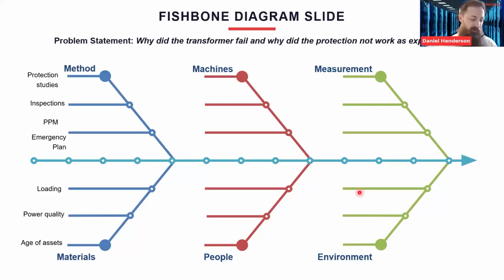The classic loading of the assets, people adding a bit here, a bit there, and whoever's ultimately in charge of the network or responsible for it is never informed until eventually you get to the overload point. But definitely some good considerations. Load subtraction should also be taken into account. Again, something to take into consideration is the loading element and especially power quality, because obviously a lot of the networks, especially back then, were designed for direct online, so very linear loading. Whereas since then we've been going to a lot of non-linear applications, which is a totally different type of load for the design of the network.